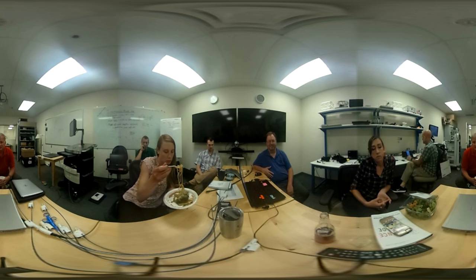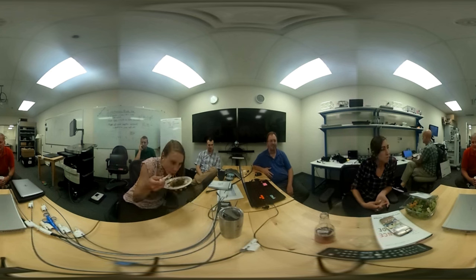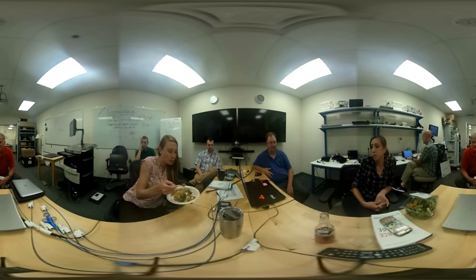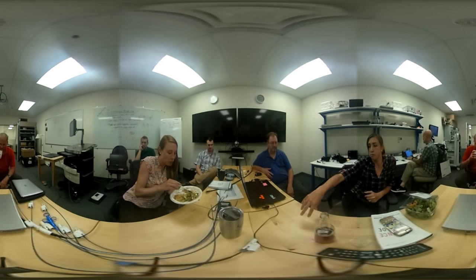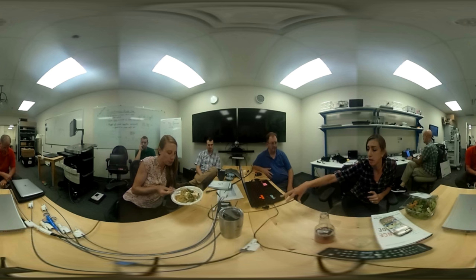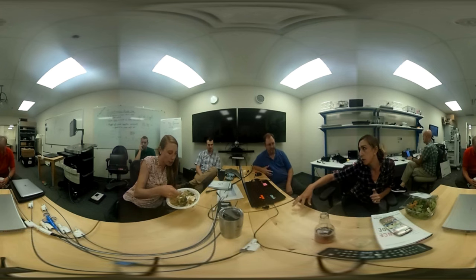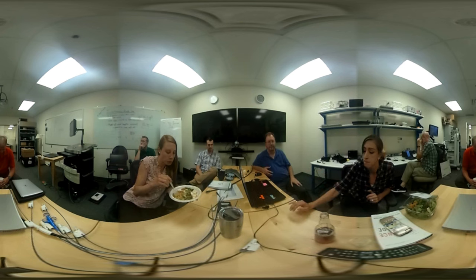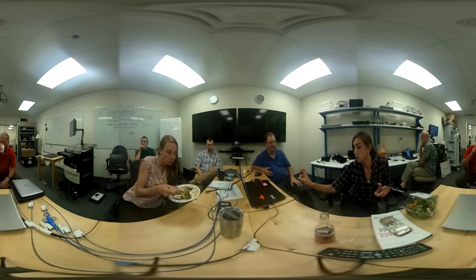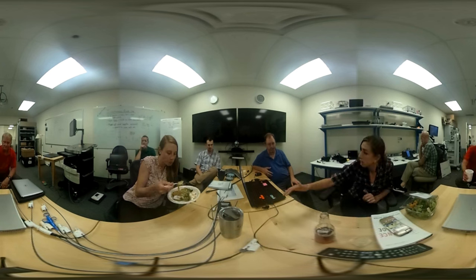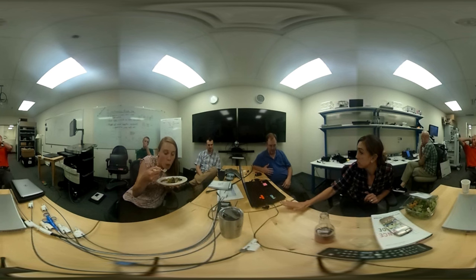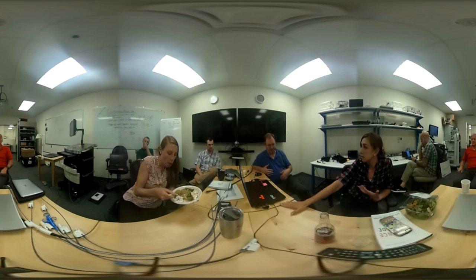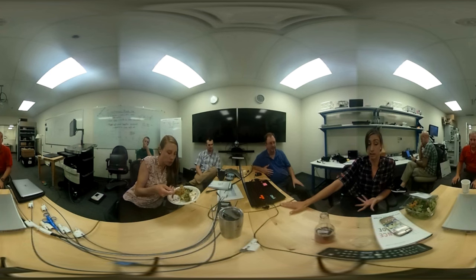So, yeah, I mean, maybe one of the things is, just describe that process. Yeah, so what we're thinking is for mechanical DD, we want to be able to assess that after what we call our reliability test, which is really the closest thing you've got to clinical use. We're going through a bronchoscope, through an S curve. So we want to establish that after reasonable use the catheter performance is still good. Yep. Still okay, right? Because we were planning on looking at continuity, but that doesn't necessarily tell us that the performance is okay, right?